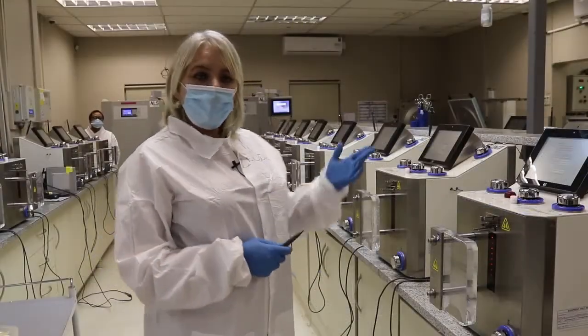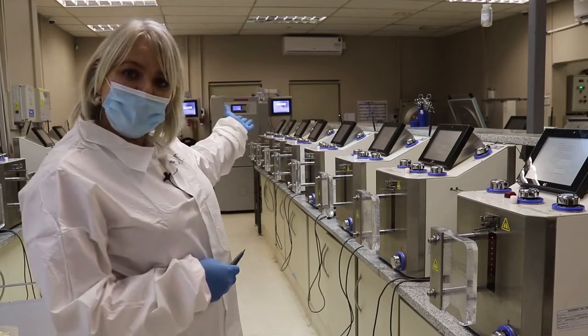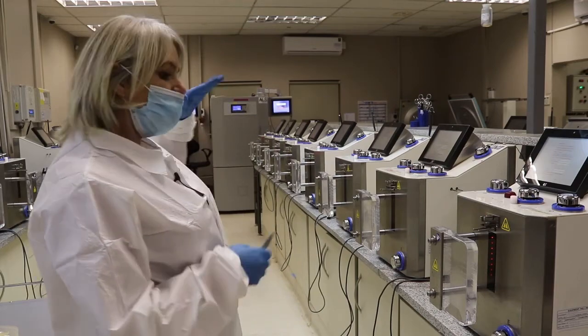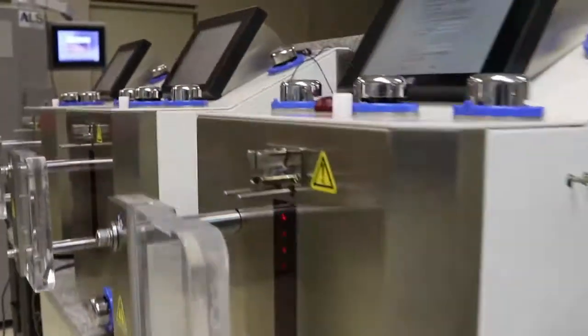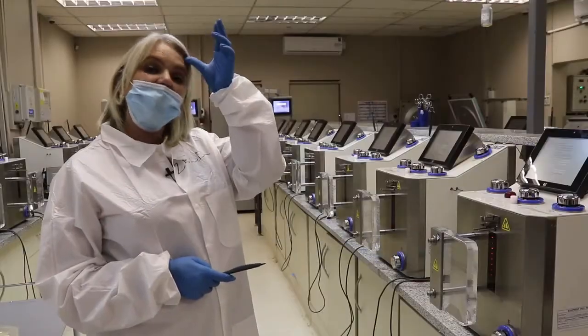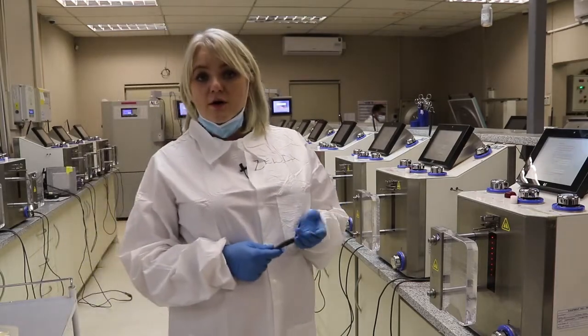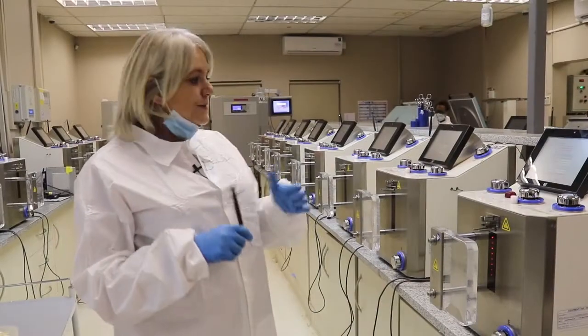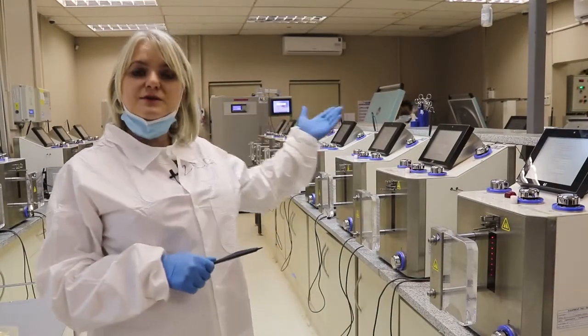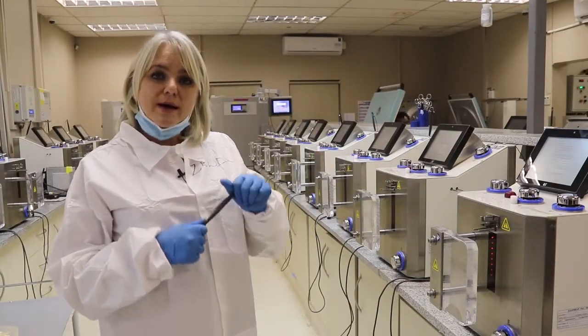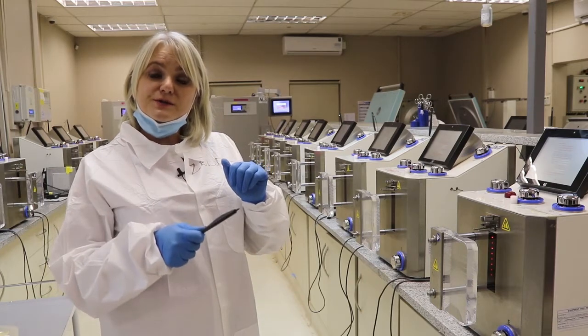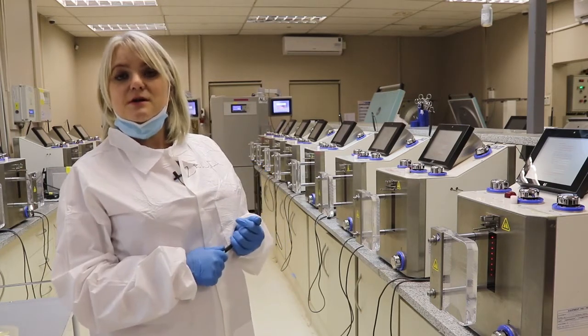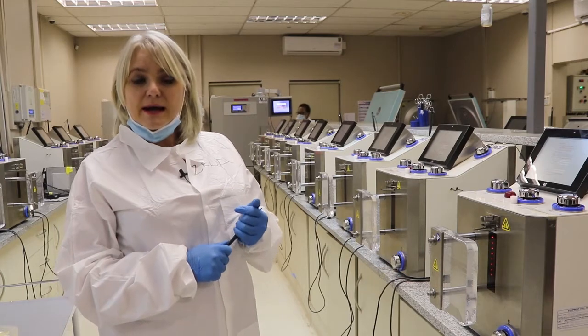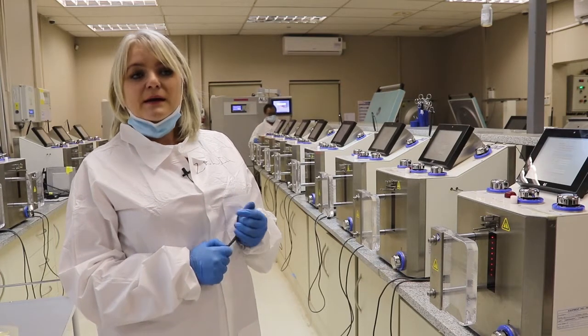So Bonnie will now load these 8 machines. We have got on this premises 13 machines. 2 of the 13 are our spare machines. Should something go wrong with a machine, they have got backup. And the purpose of demonstrating on the 8 machines is to show that one front or first line processor can manage 8 machines on their own without any wasted time in between.